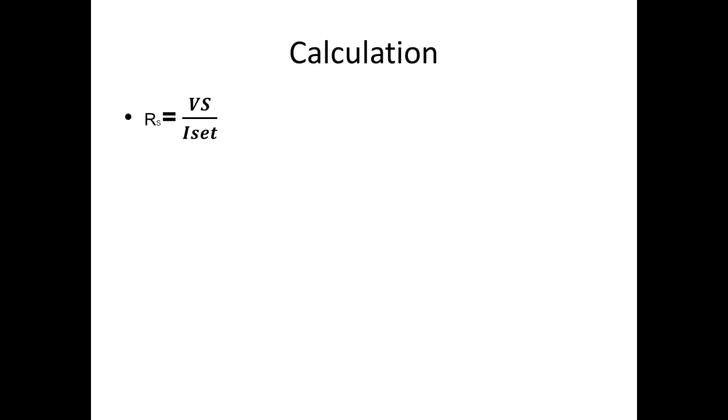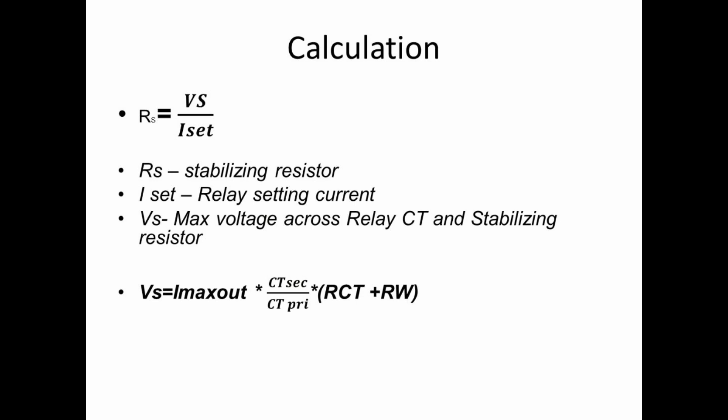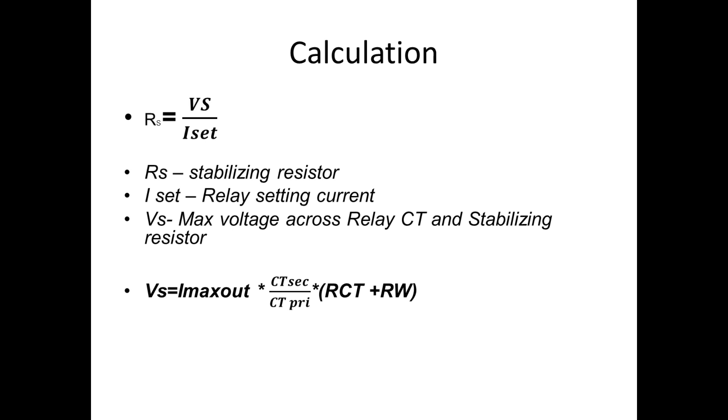Now, we are going for calculation. RS is equal to VS by ISET. The abbreviation for this equation is: RS is stabilizing resistor. ISET is relay setting current which we are going to set on relay for pickup and issue tripping. VS is a maximum voltage across the relay CT and stabilizing resistor. To find this, we have another formula for calculating, i.e., VS is equal to Imax out into CT secondary by CT primary into RCT plus RW. Imax out is a maximum external fault condition current. RCT is CT secondary resistance. RW is a total resistance of the wire conductor.